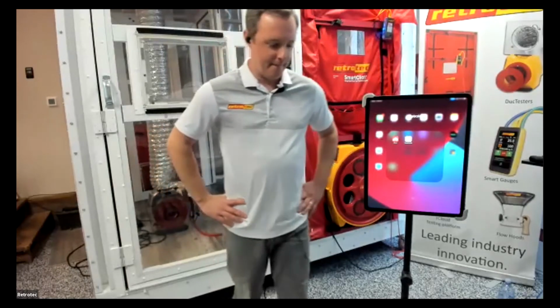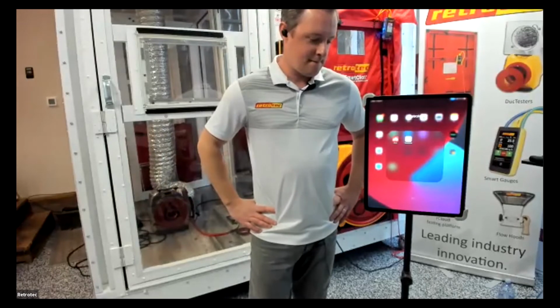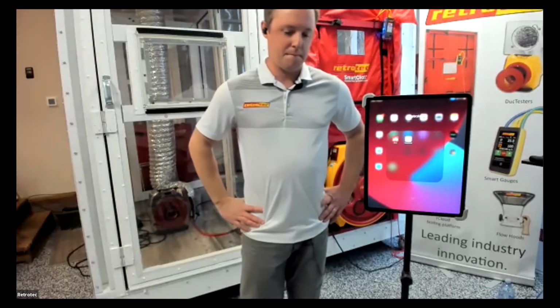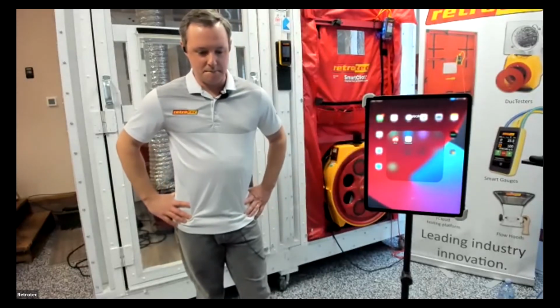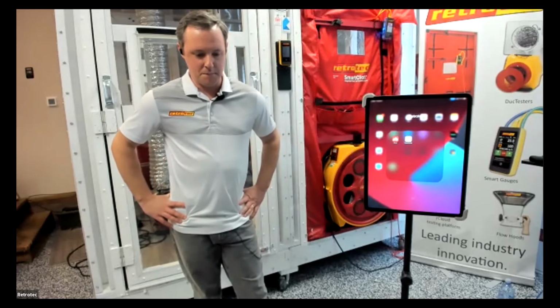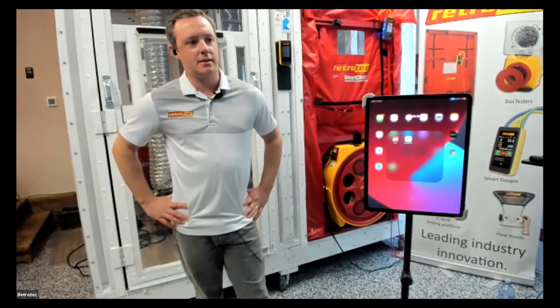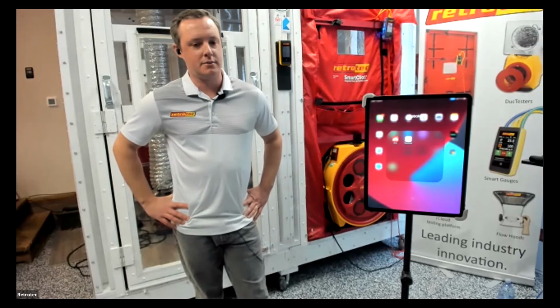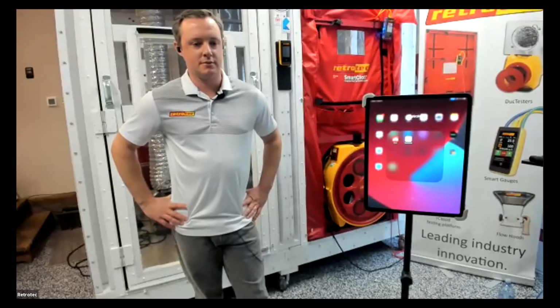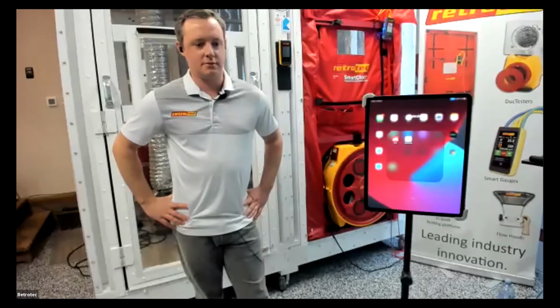It can be confusing when you're doing the duct leakage outside because you want 0 on the gauge if you're not referencing outside with the duct tester. So before you start the fan, you can look at channel A and see where you're at, and then just slowly ramp up the fan like Sam was doing and see that number drop, and that'll help you keep it straight. Because that is something that is pretty confusing. I get questions on that a lot.